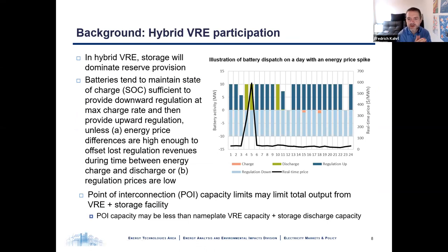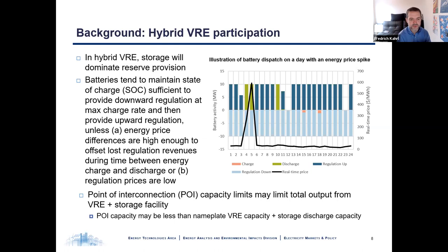For hybrids, the economics of market participation are very different and are driven by battery economics. Batteries typically like to charge up to a state of charge sufficient to provide upward and downward reserves and then just sit there, unless energy prices spike — making energy arbitrage economic — or reserve prices are really low. An interesting dimension for hybrids is point of interconnection capacity limits — the maximum power a facility can inject into the grid. In our base case, this is capped at the wind or solar facility nameplate capacity. For example, with 15 MW of solar and 10 MW of battery capacity but a 20 MW POI limit, the total energy and upward reserves that can be provided is 20 MW, affecting battery charge and discharge operations.